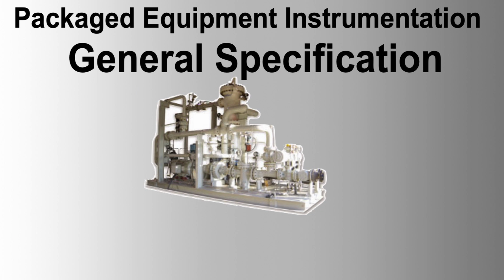Instrumentation test. Skid-mounted instrumentation must undergo bench and in-situ calibration, wiring continuity and insulation tests, air leakage tests, process impulse line tests, and pneumatic or nitrogen tests. All test equipment must be certified and provided by the vendor. Pneumatic tests. Pneumatic equipment should be tested for leakage using dry air at 110% of maximum working pressure, and functional tests should verify proper operation over the full range of input signals.